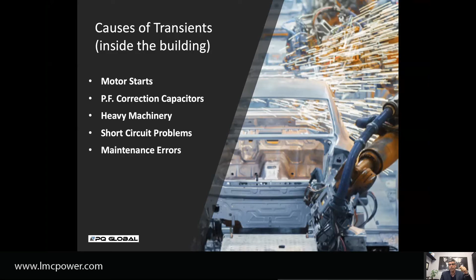So we went through and looked at their one-line diagram and already provided a solution for their facility to have continuous power. Motor starts, power factor correction capacitors, any kind of heavy machinery turning on and off will generate a transient—a big spike in current at that moment. Short circuit problems and maintenance errors will also create a short and generate a transient that spreads throughout the electrical system.